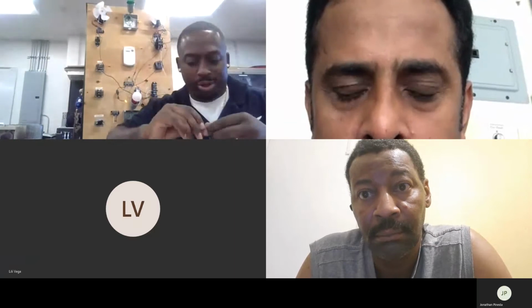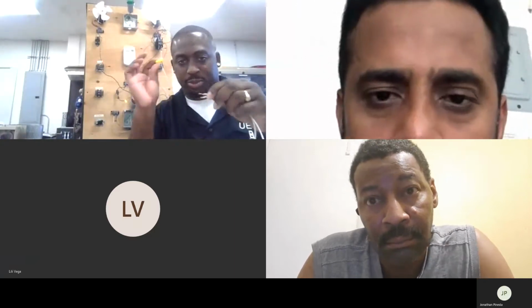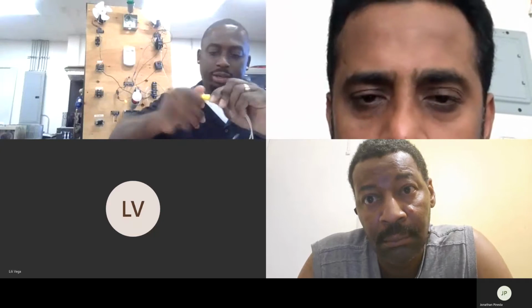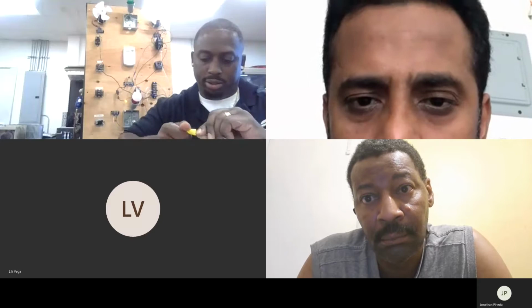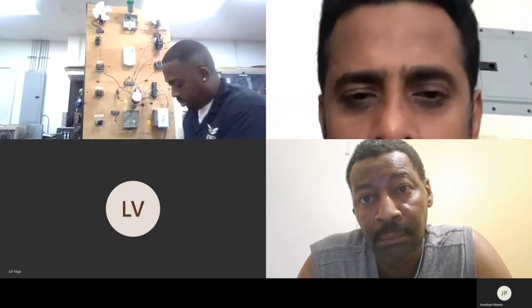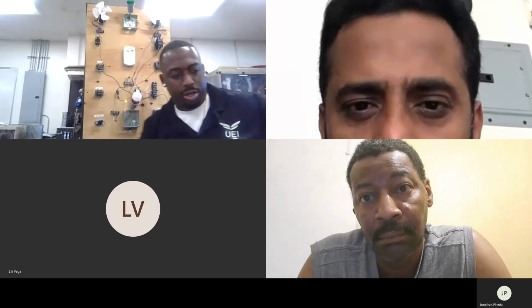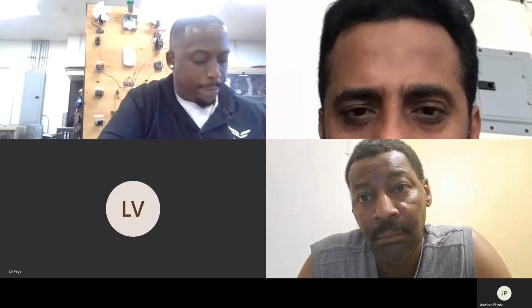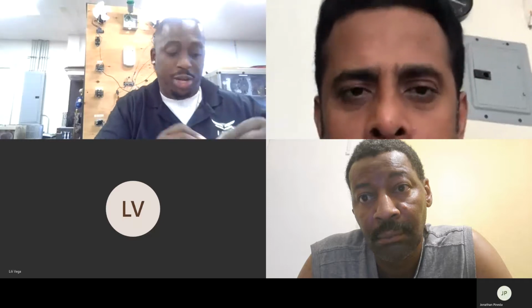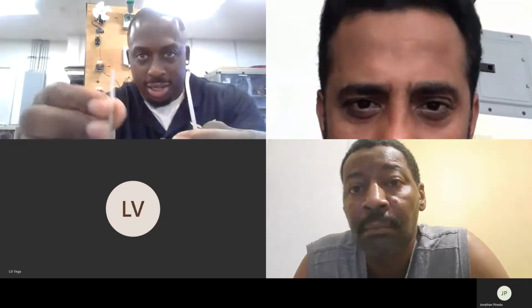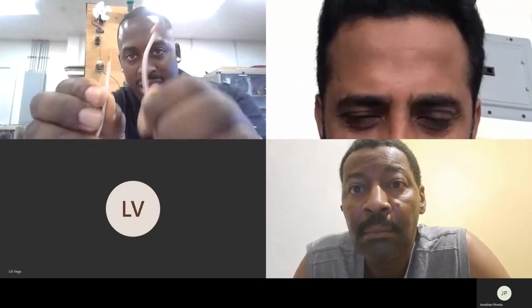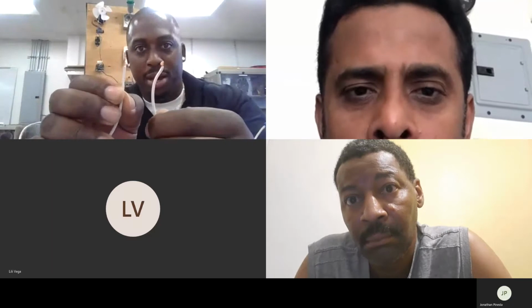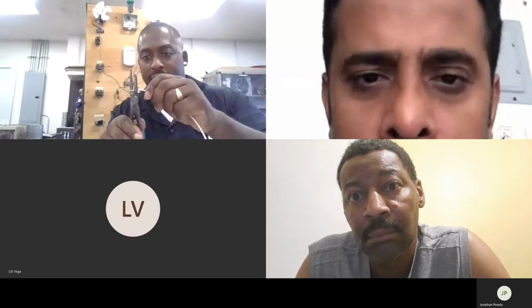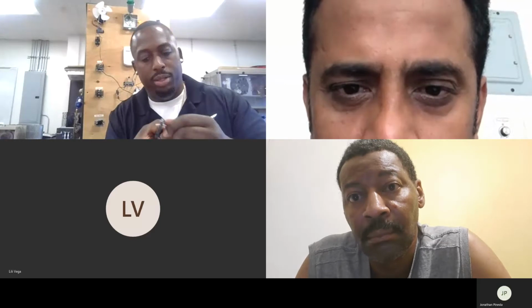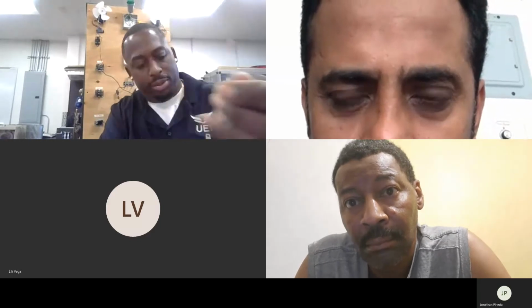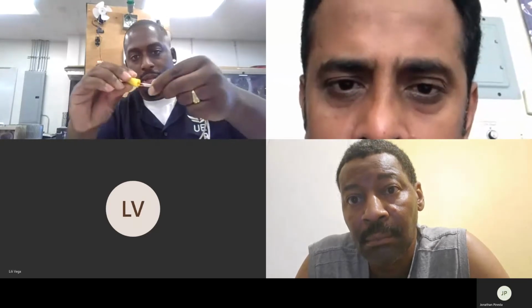So, quick little review. You hooking up your wire nuts. You don't want to twist them. You want to let the wire nut do the twisting. Put them next to each other, twist. That ain't going nowhere. All right. Whoa, it did go somewhere. I had a feeling that, see, notice one stuck in there real good and one didn't. This one has plenty of wire to grab. This one does not. So I need to re-strip that. That's poorly stripped, and that's why it just came out on me. So I'm gonna go ahead and cut that, re-strip it. Now I got something to grab. Let's put those together.